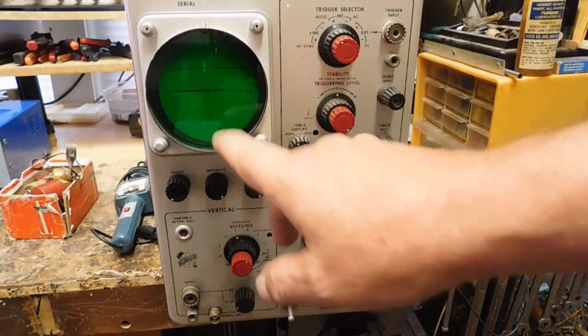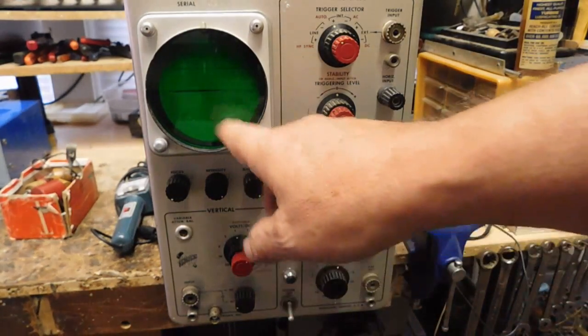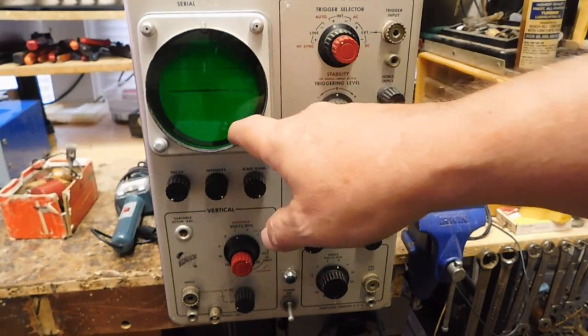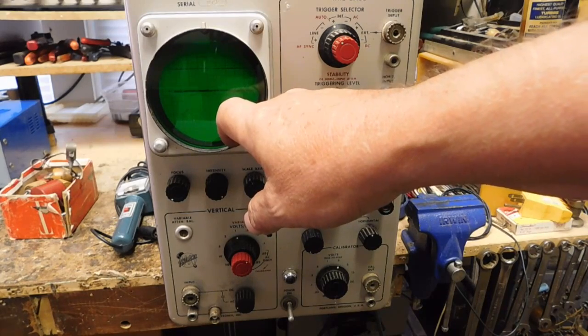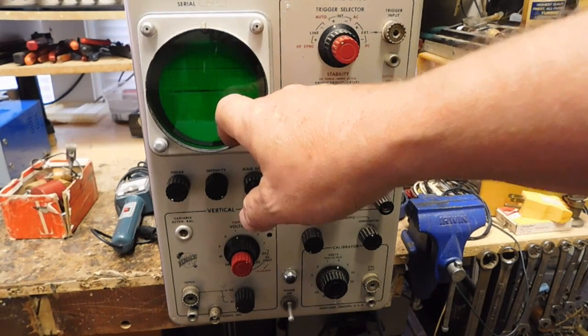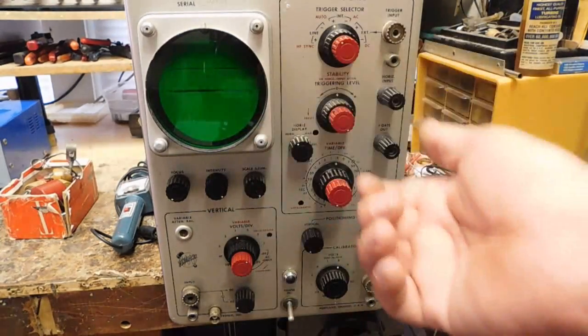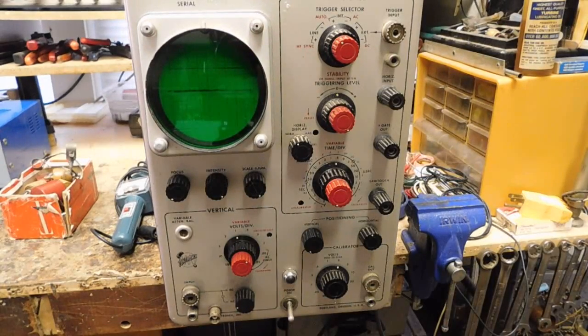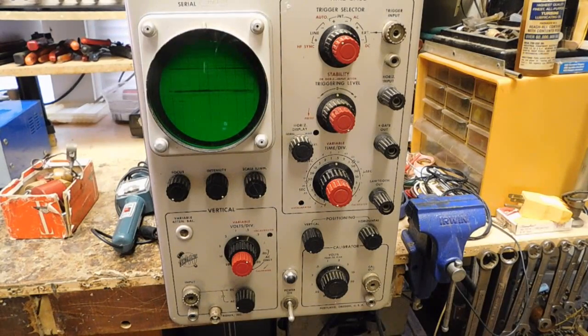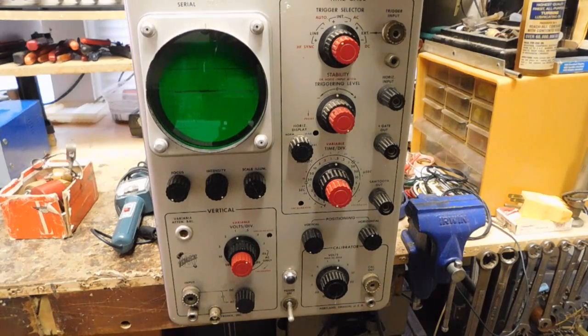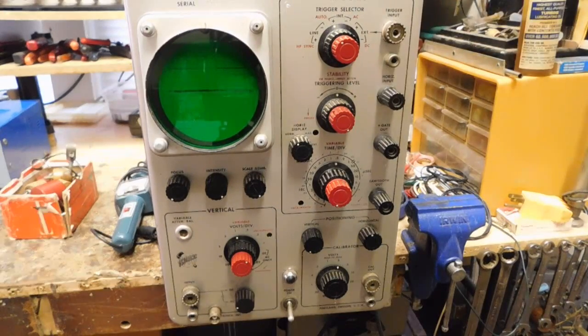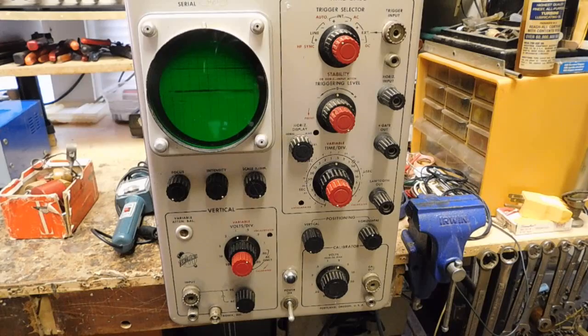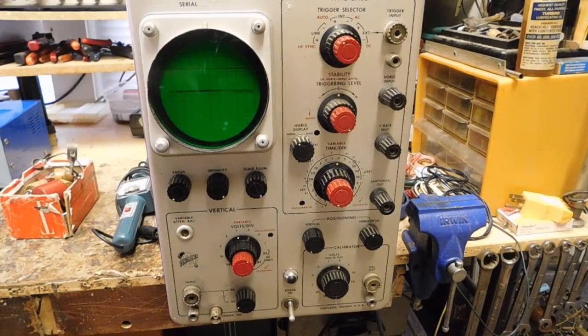The other thing too is after it's on for a little bit, when I try to reduce the illumination on the screen, I should be able to take it to 0, but after it's on for, say, 25 or 30 minutes, it gets where you can't do that. You can really brighten it up, but you can still plenty see a trace going across there at minimum intensity. So there's a problem in that circuit as well. I believe the grid bias is off some, or floating off, probably a resistor or capacitor or both. So here in a minute I will open it up and show you, but first I want to show a couple other little things that I got.